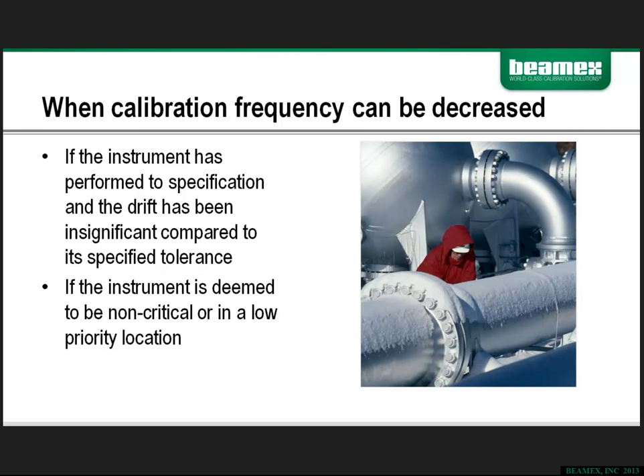For example, if you have a transmitter that is on a 6-month calibration cycle, meaning it's calibrated every 6 months, and you were to go for 3 successive calibration cycles with little to no drift, and that unit testing well inside its tolerance, then that would typically justify an increase of 50%, thus taking that calibration interval from 6 months to 9 months. And then if you were to go 3 more intervals and see the same results, then you could once again increase that calibration interval from, say, 9 months to a year. So that would effectively increase that interval by 100% over a 6-cycle period.